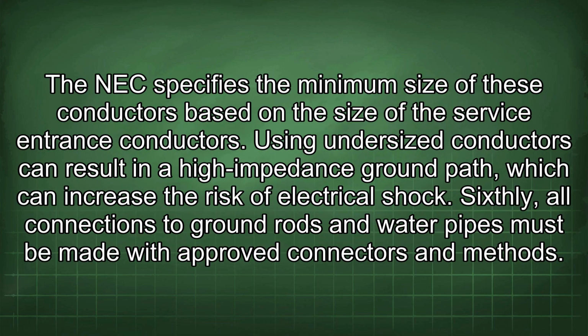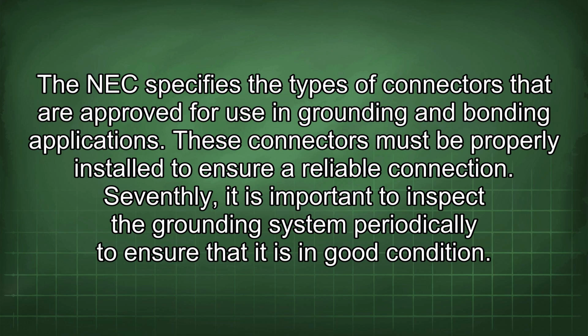jumpers. The NEC specifies the minimum size of these conductors based on the size of the service entrance conductors. Using undersized conductors can result in a high impedance ground path, which can increase the risk of electrical shock. Sixthly, all connections to ground rods and water pipes must be made with approved connectors and methods. The NEC specifies the types of connectors that are approved for use in grounding and bonding applications. These connectors must be properly installed to ensure a reliable connection.